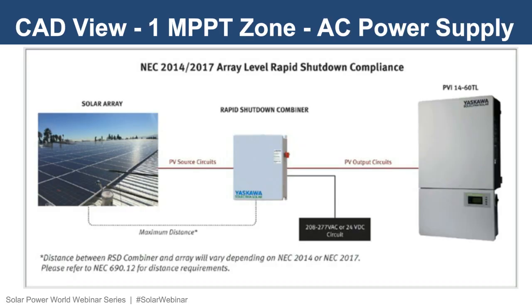Here is a simplified schematic view of how the RSDCOM can be used in conjunction with the Solectria TL string inverter to meet the array level rapid shutdown compliance of either NEC 2014 or 2017. On the left, you see a picture of a solar array with your PV source circuits inputted directly to the rapid shutdown combiner. The output of this combiner are PV output circuits, which feed directly into the PVI 14 through 60 TL string inverter. You'll see depicted at the bottom, the RSDCOM location should be within the maximum distance required by the National Electric Code, 10 feet for NEC 2014 or 1 foot for NEC 2017. Additionally, you see the need of the external control power source, 208 to 277 volts AC, which is easy to be provided from the same source of electricity providing power to the inverters.